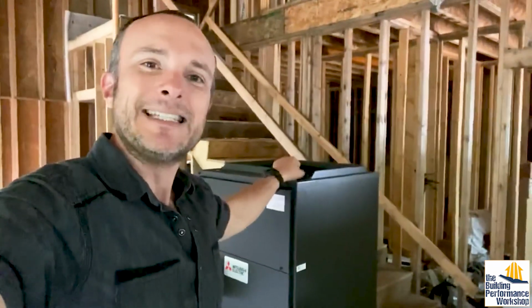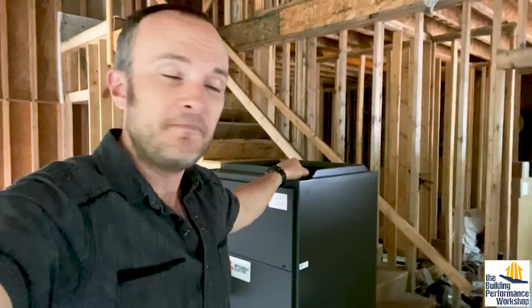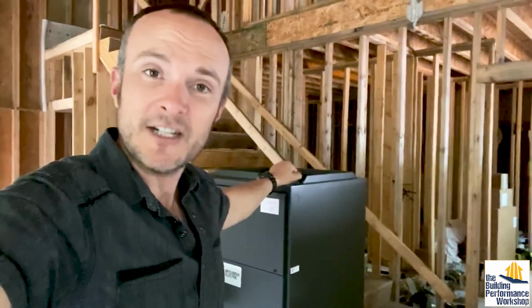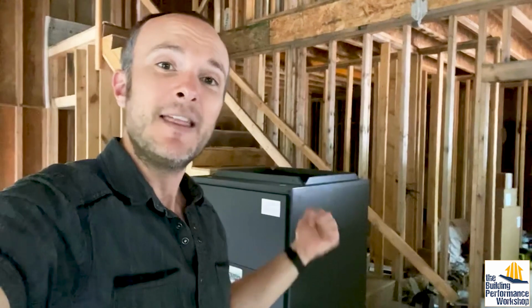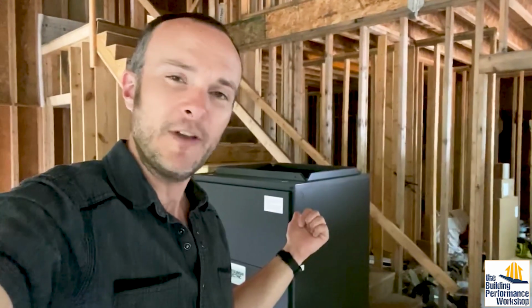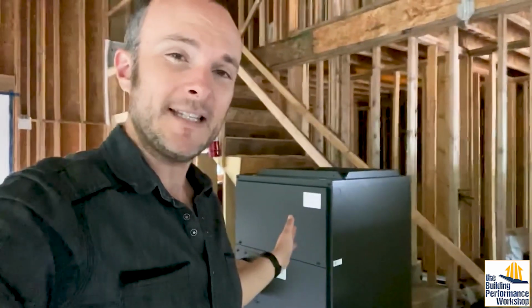Ducted systems are very useful for a lot of things. They have ductwork built in, so you can distribute the 800 CFM moving through this to dehumidify the entire living space and filter it. We have a HEPA filter system going onto this from Fantech. The dehumidifier we'll use is an Ultra-Aire 105, a discontinued model—the closest replacement is a 155 XT. We'll cover that more when we install it, but that's what this ducted system is going to do.